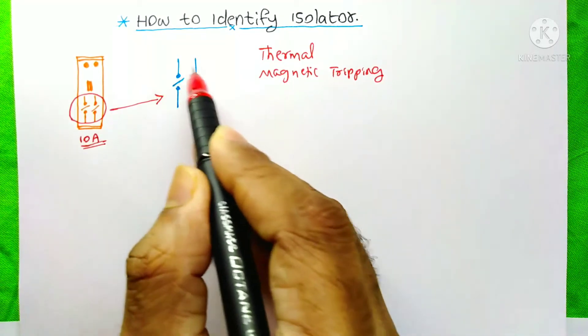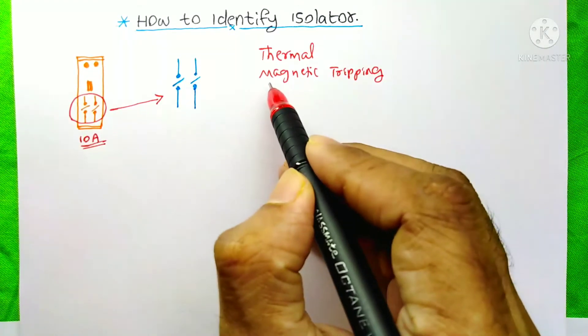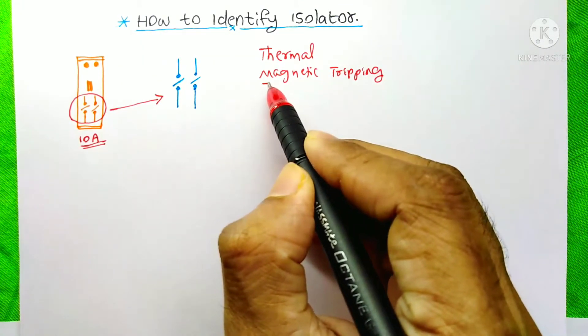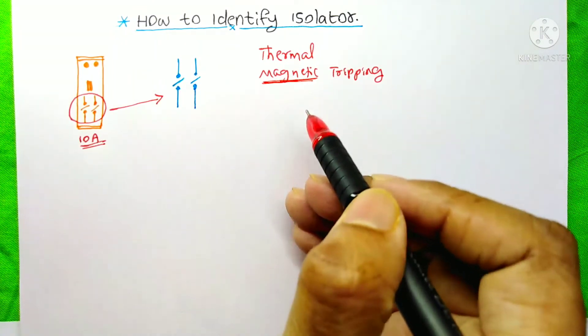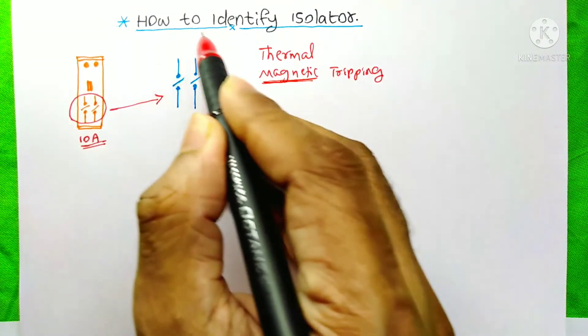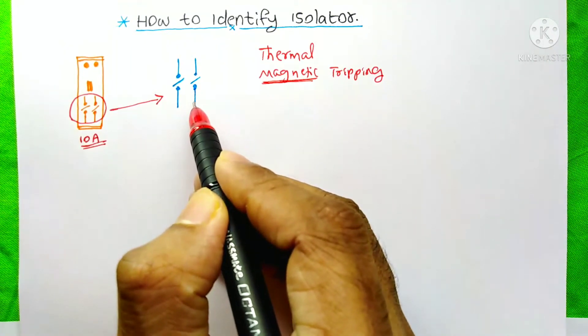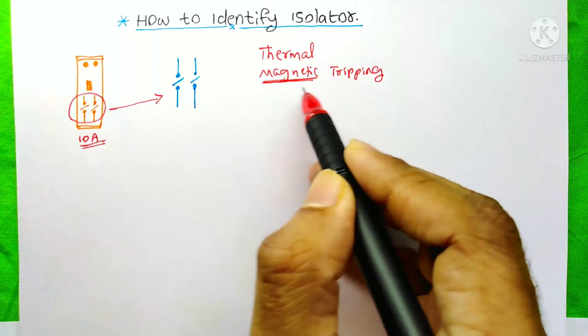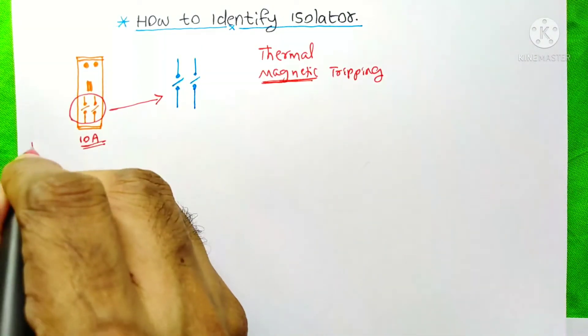That means it will not get tripped automatically. And at the same time it will not give you the protection of this magnetic tripping also. That means if any short circuit happens on this circuit then this isolator can't trip automatically because it will not give you any magnet tripping characteristics.